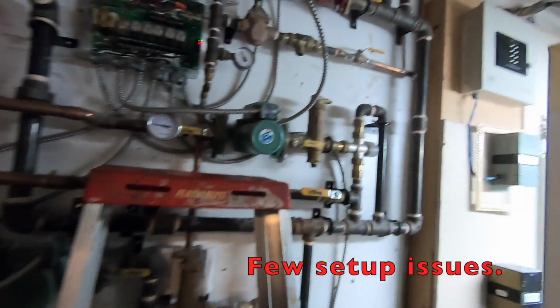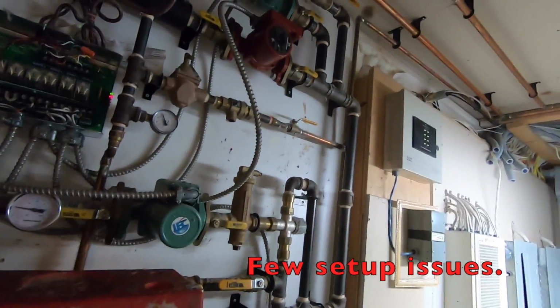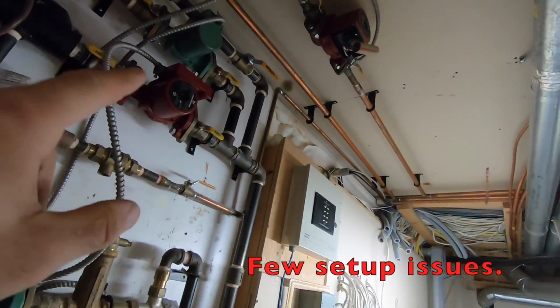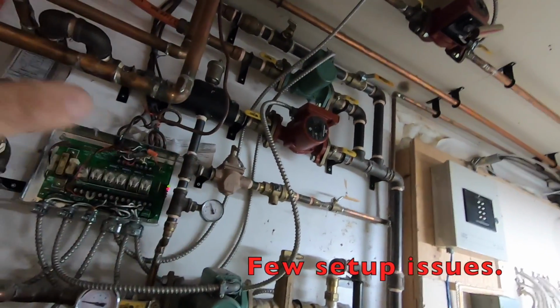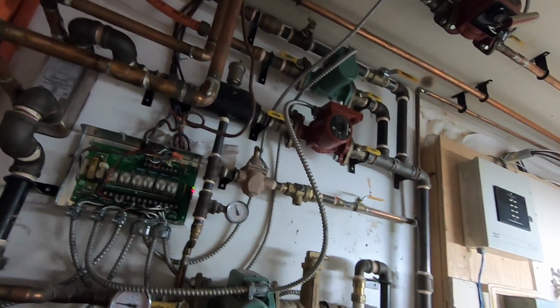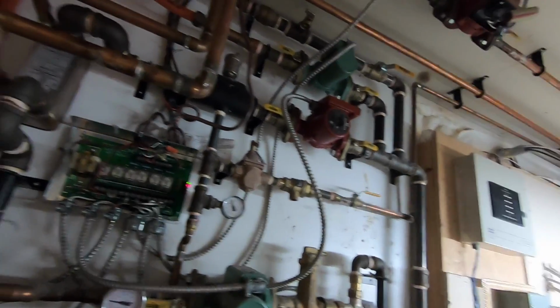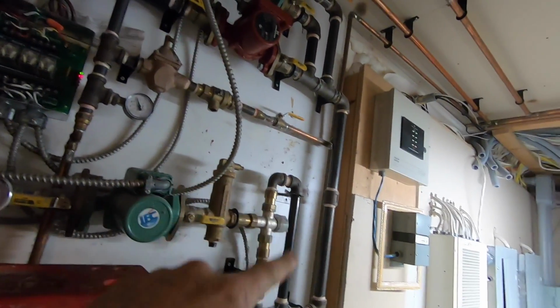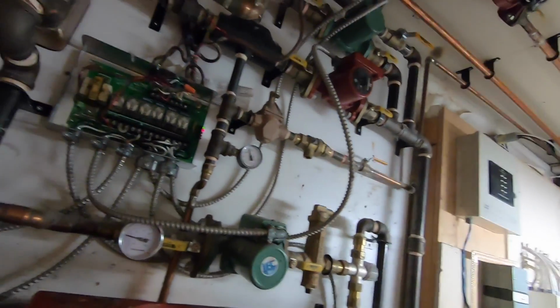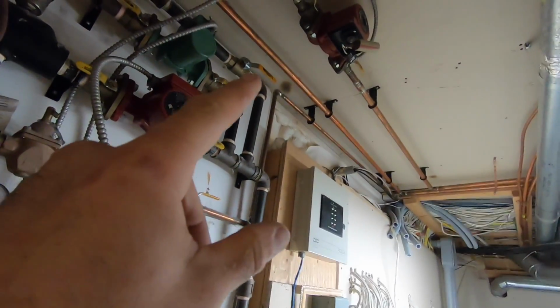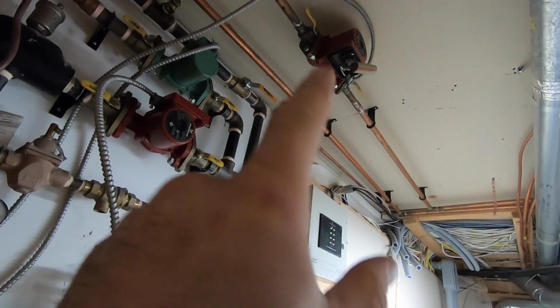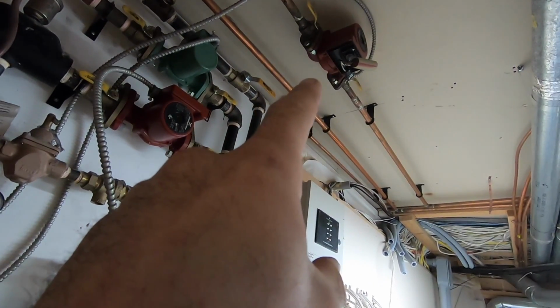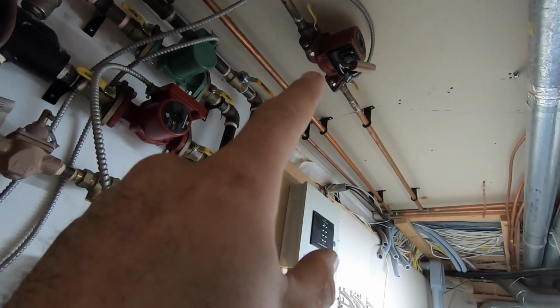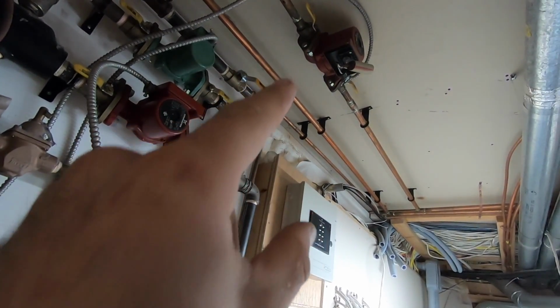What's going on, guys? Okay, I'm at the service call. What we have here is different pumps for different heat calls. Got auxiliary for a pool, auxiliaries for floor warming. Then we got the main loop that goes to the heat exchanger. The problem was, the way they set it up, this pump here for the primary loop from the boilers is on all the time.